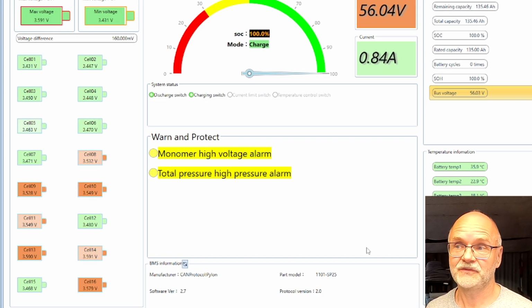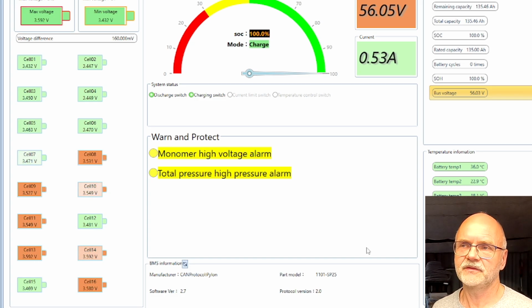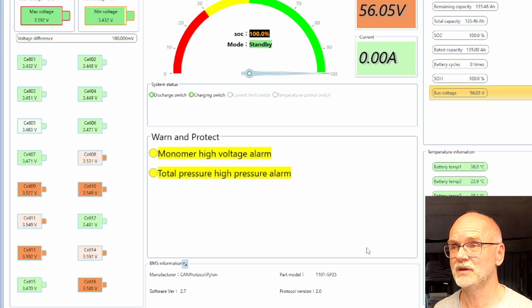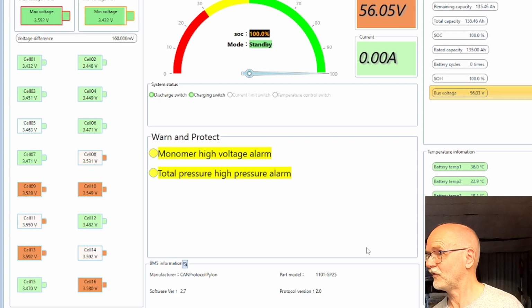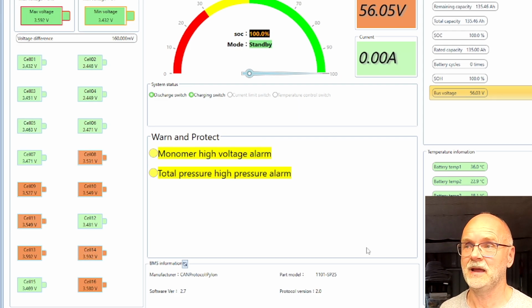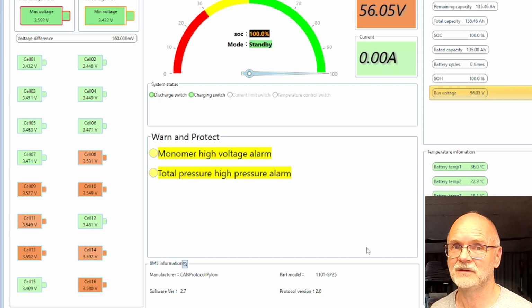We can now see a second alarm coming up, the overall pack voltage high voltage alarm, set to 56 volts. So now we've got a 160 millivolt deviation, and the voltage of the green cells is rising very slowly. The current has even tapered off to 0 now, but we're still charging with 560 milliamps. Around 600-700 milliamps is the cutoff for the SEPLOS BMS to measure anything.